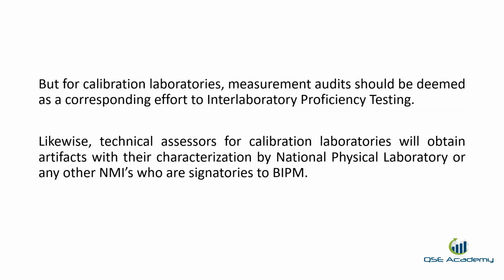But for calibration laboratories, measurement audits should be deemed as a corresponding effort to inter-laboratory proficiency testing. Likewise, technical assessors for calibration laboratories will obtain artifacts with their characterization by National Physical Laboratory or any other NMIs who are signatories to BIPM.